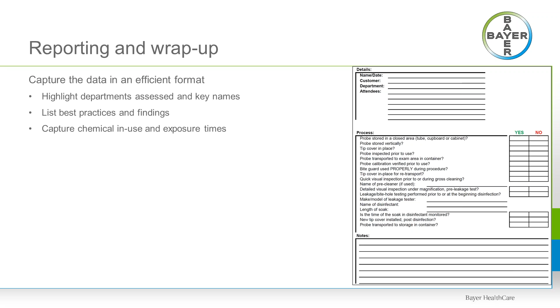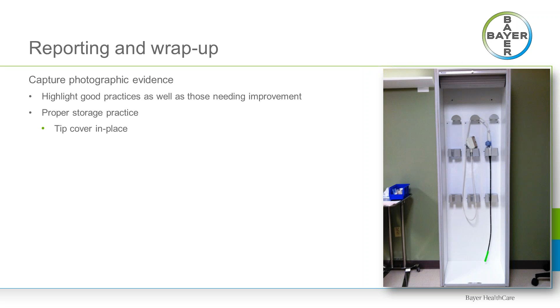Photo documentation can really aid in capturing good practices as well as those in need of improvement. Here it can be seen that the probe is stored properly and that a tip protector is in place. Here is an improperly staged probe in an OR environment. It's at risk for physical damage. One bump into the scanner and the probe uncurls and falls to the floor.